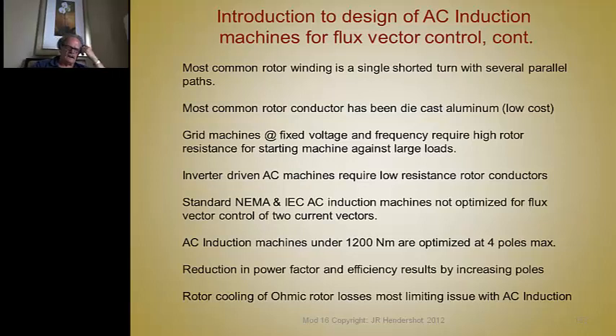As we said, the rotor windings consist of single shorted turns with a lot of parallel paths for the current to flow, and those parallel paths go through what we call the rotor slots, through the rotor bars. They're shorted from end to end with end rings. But the current doesn't flow in the same direction from one end to the other in all the rotor bars. Some of the bars will go from left to right, let's say, and that forms a north pole, and then adjacent on either side of that group of bars, you'll have the current flowing in the opposite direction, and that creates the south pole. And then as it rotates, the bars in between those adjacent poles have a current direction reversal taking place. So it's very complicated what goes on in there.